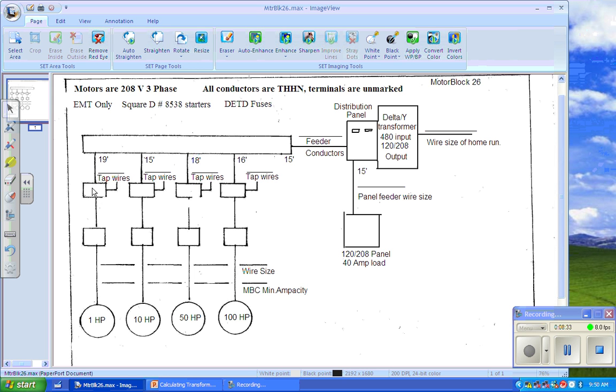And we could supply all of the control circuits with one control transformer, right? Because a control transformer is not going to see a lot of load. All we have is some push buttons being pushed, and what's it doing? It's just pulling in a little coil. And we've measured the current that's in those little coils, right? And it's way less than an amp, right?